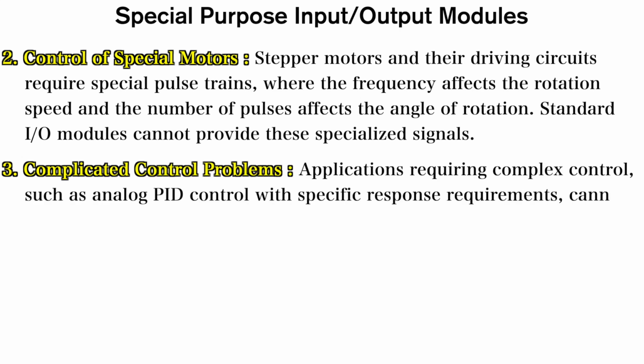The third case is complicated control problems. Applications requiring complex control, such as analog PID control with specific response requirements, cannot be handled by the standard modules. So here also we use the specialized input output modules for PLC operation.